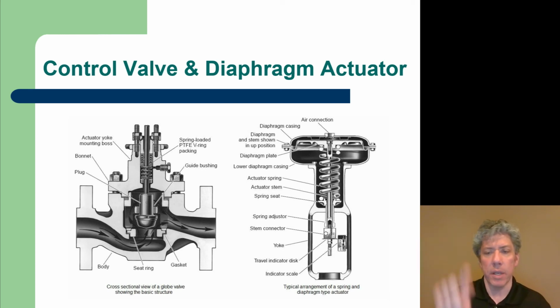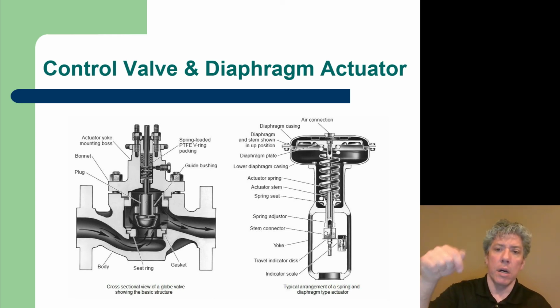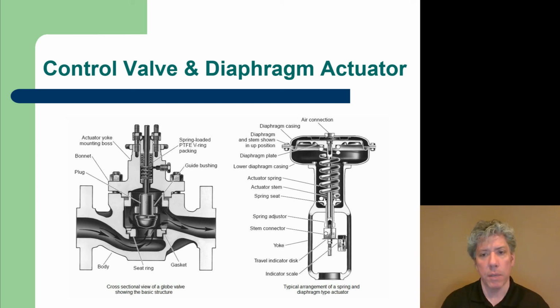And then there's a stem there that can be moved up and down that's connected directly to the stem of the valve to pull the stem of the valve or push it in or out of the valve and control flow. The way this thing works, there's actually a diaphragm at the top, and it's sealed. The upper chamber is sealed from the lower chamber by the diaphragm, and you see the air connection at the top. When you increase the pressure in the air connection, that pushes the diaphragm down against a spring. And so you see that spring there, partially in cross-section. The bottom end of that spring is grounded, in other words, connected to the yoke and does not move relative to the yoke, but the upper end of the spring moves with the diaphragm. Of course, the spring is pushing up, trying to resist the diaphragm, but as you add air pressure, it pushes the diaphragm farther and farther and compresses the spring, driving the stem of the valve into the valve body.